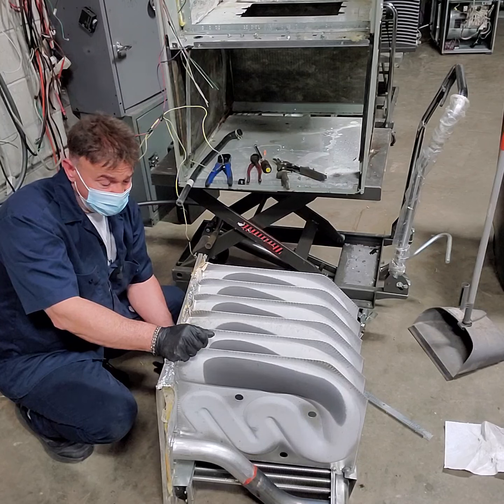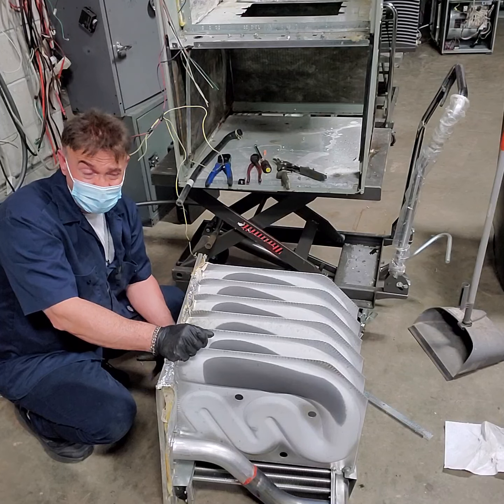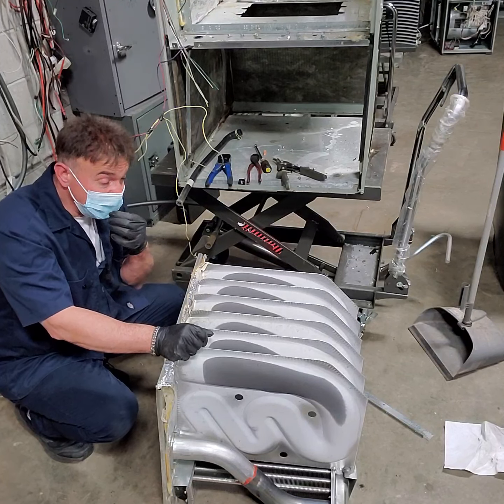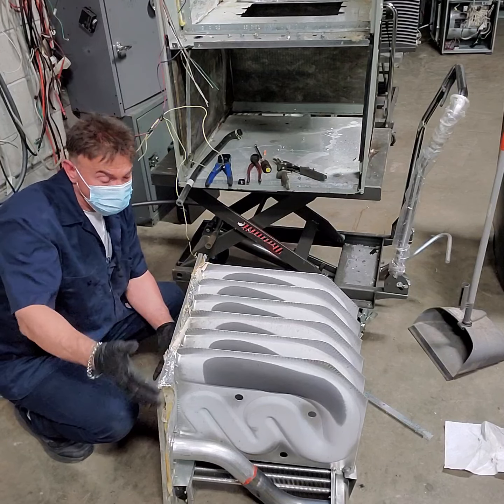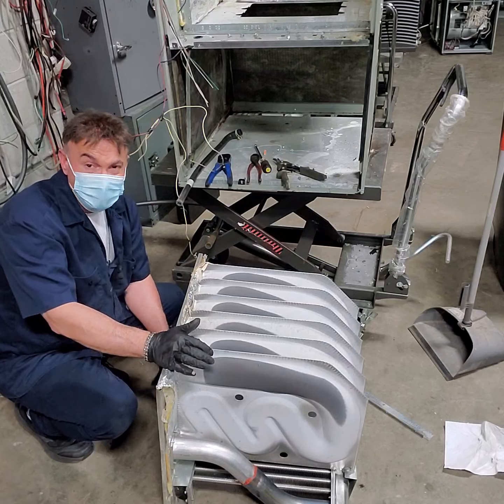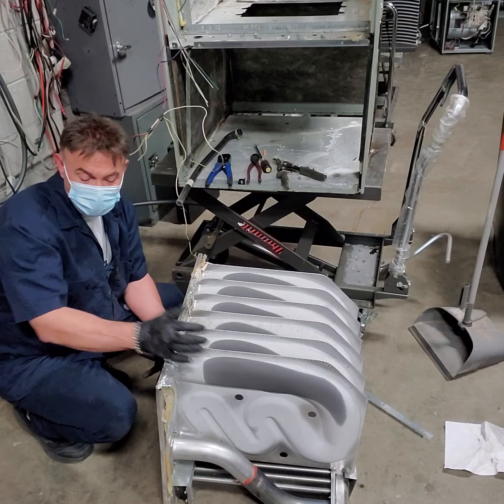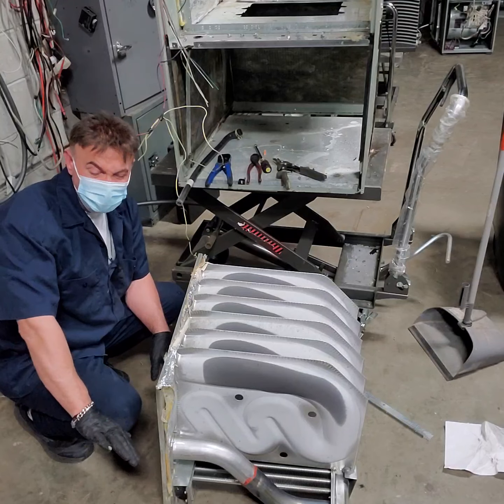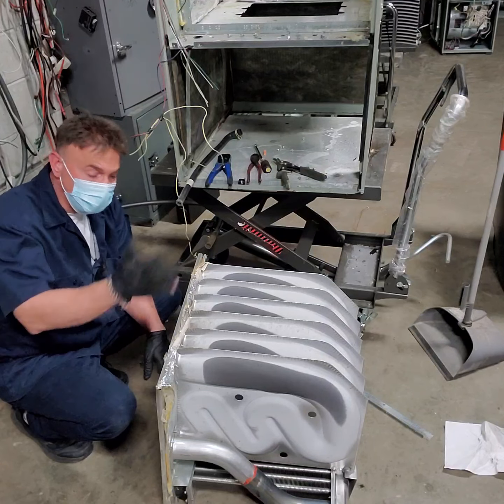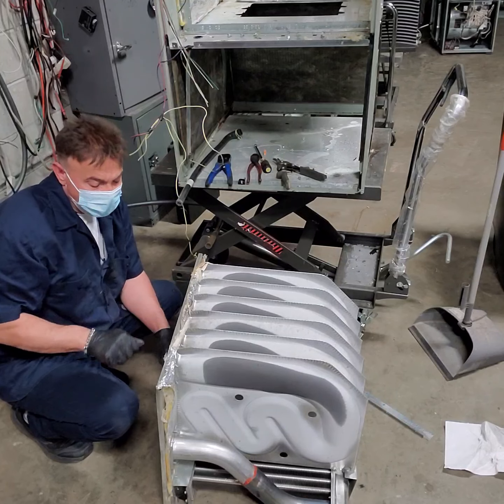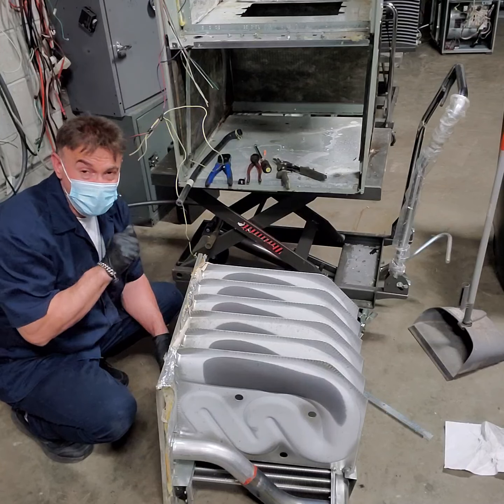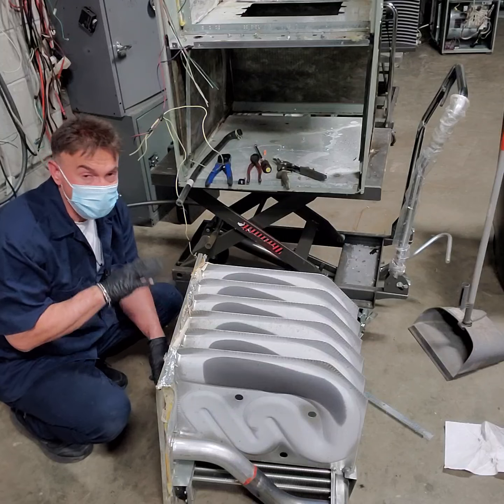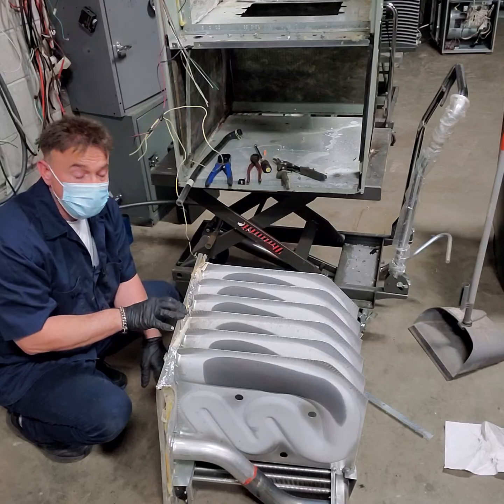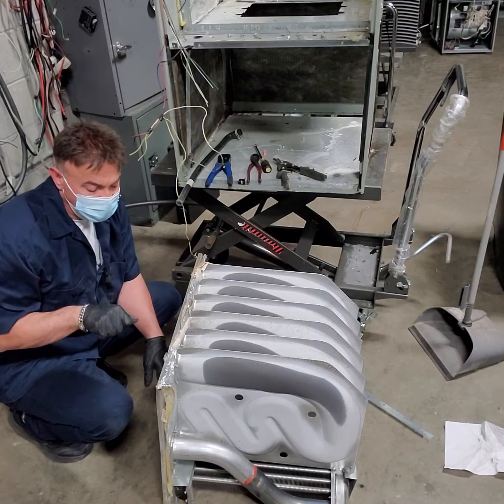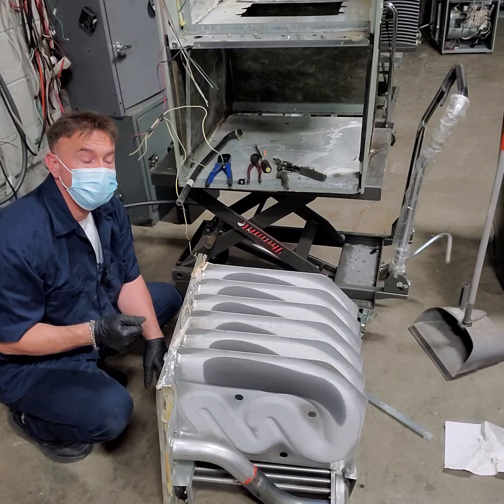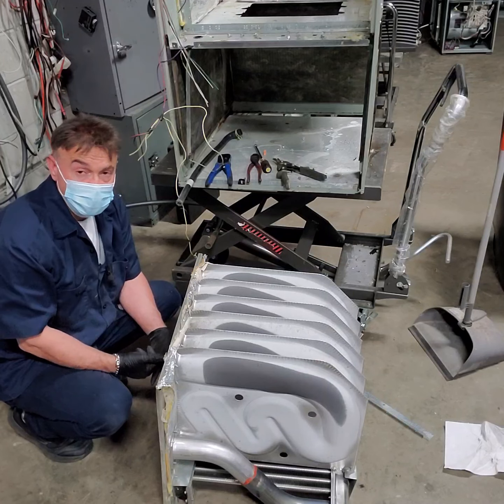So basically you're heating the house so quickly, with a lot of heat in one section of the house more than the other, because it depends on how close you are to the burners. That's why when you're sitting next to a register, you can feel the air is really hot. It bothers you. You just want to move. So the idea is, I couldn't show you on this furnace how to adjust the gas valve because there was a problem with the inducer motor. But you need to adjust the gas valve in a way where you have anywhere between 100 to 130.